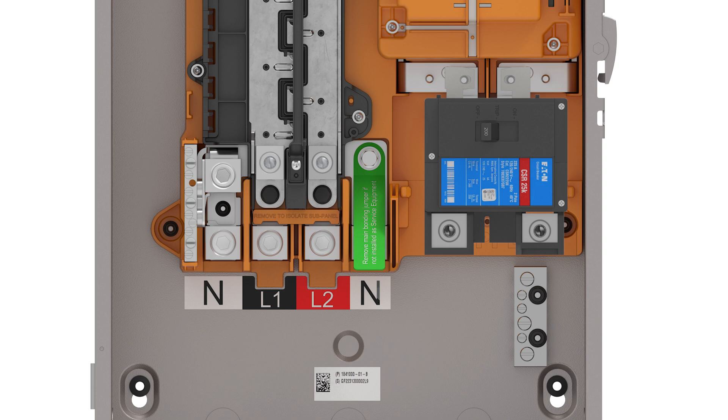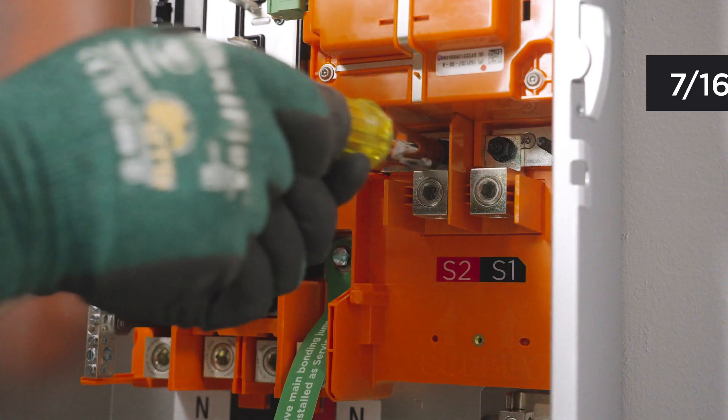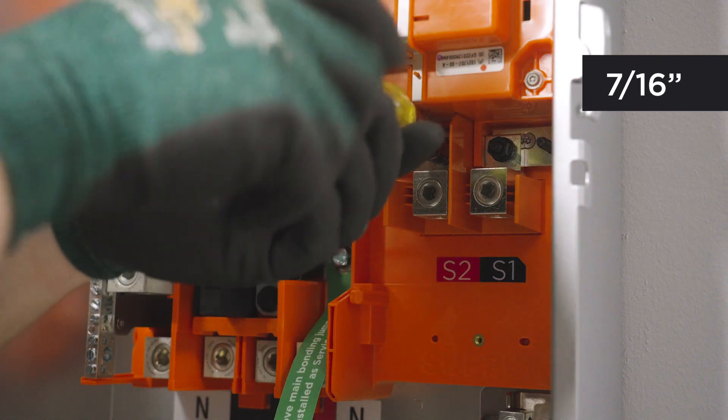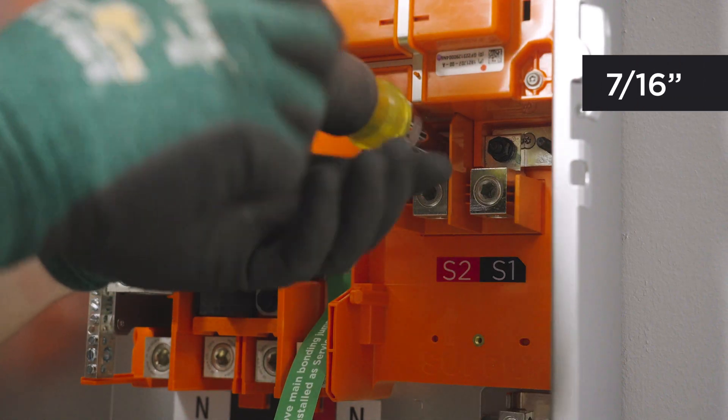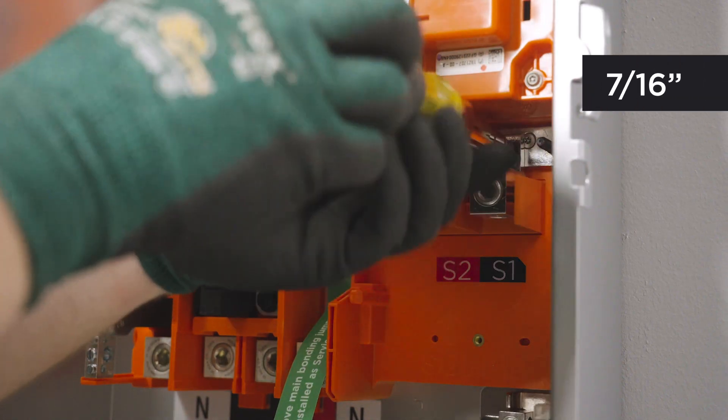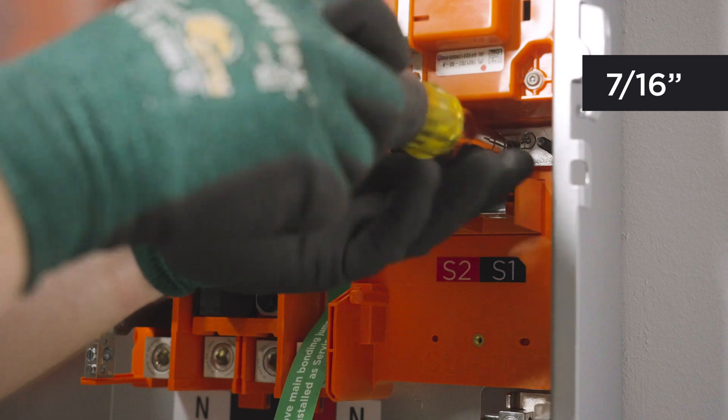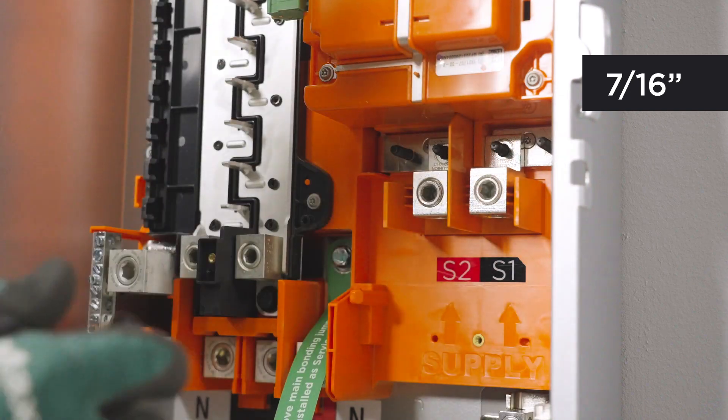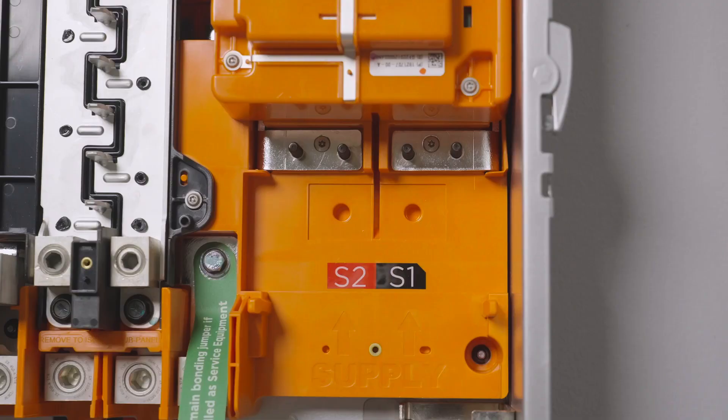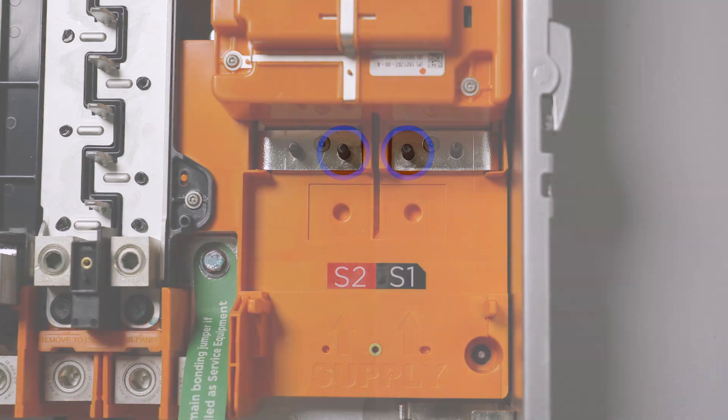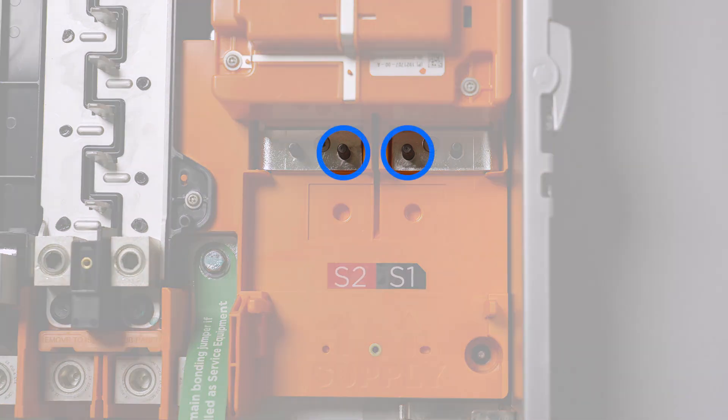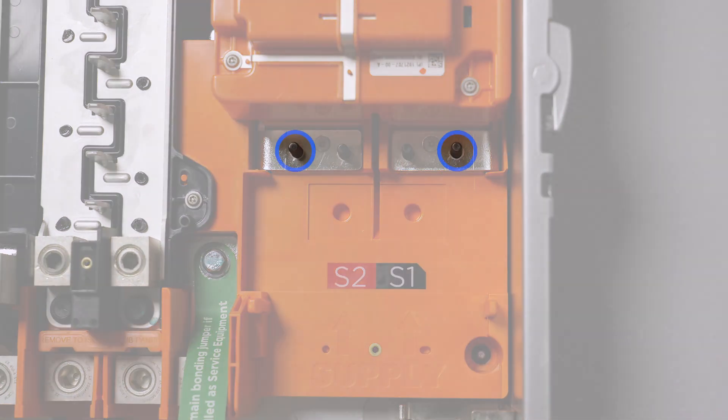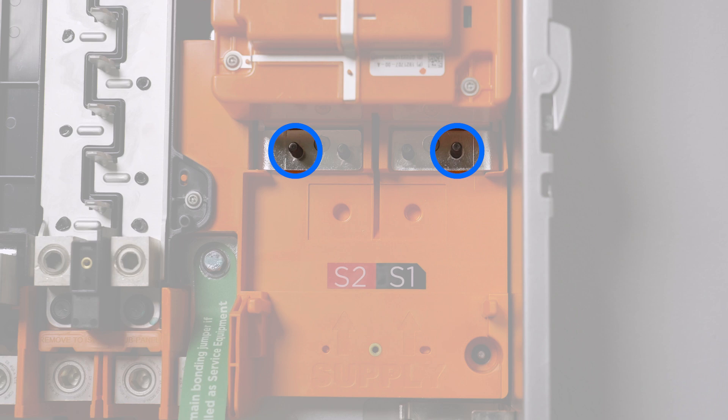To install a main breaker, use a socket to remove these nuts securing the S1 and S2 lugs to the supply bussing. Identify the two sets of threaded posts that are used with main breakers. The inner set of posts are used with Eaton main breakers. The outer set of posts are used with Square D main breakers.